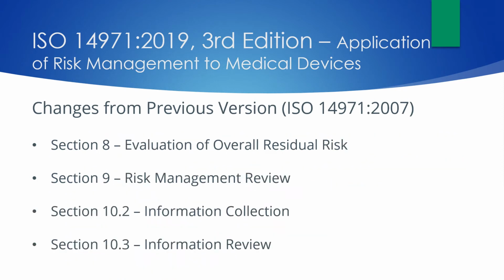Section 8, Evaluation of Overall Residual Risk, has an addition of disclosure for residual risk statement. The standard requires manufacturers to describe the method for evaluating overall residual risk, define criteria for acceptability of individual risks and overall residual risk, perform a benefit risk analysis on individual residual risks not meeting the criteria as well as on the overall residual risk, and to implement processes to continuously update risk management documentation, including with production and post-production data. It's important to note that when evaluating risk, accepting too many small risks can constitute one big risk.